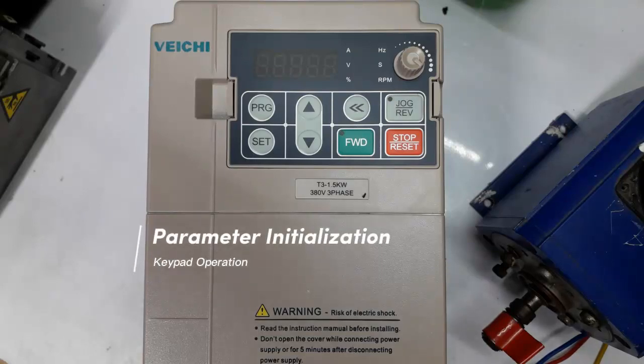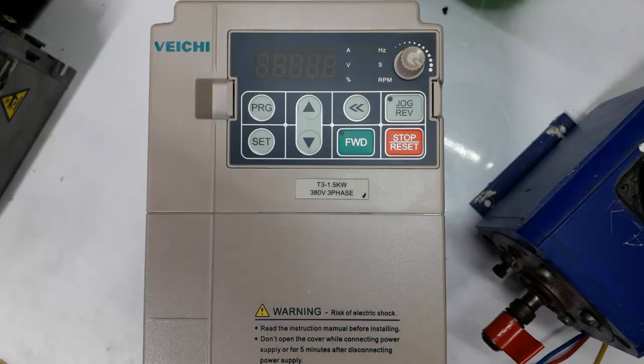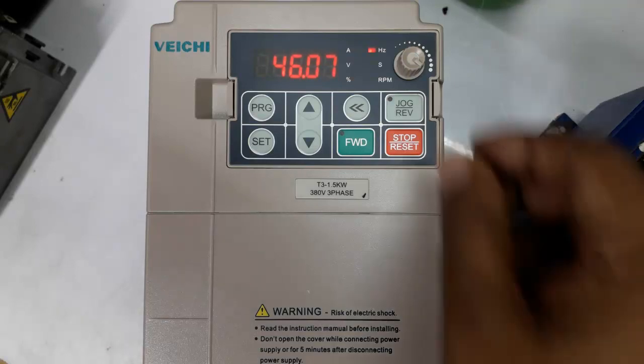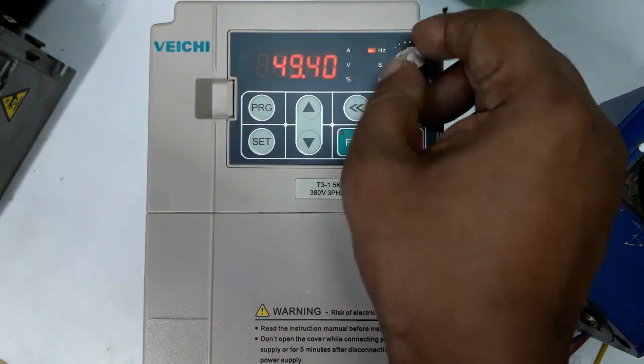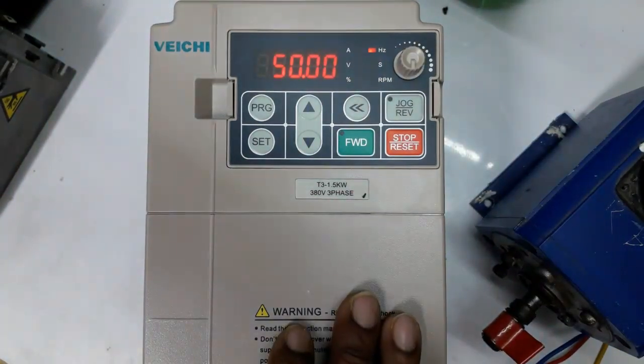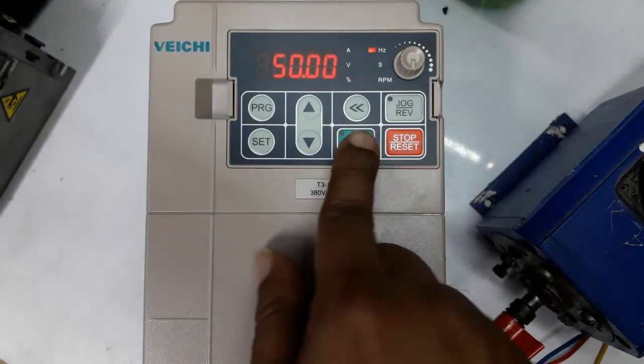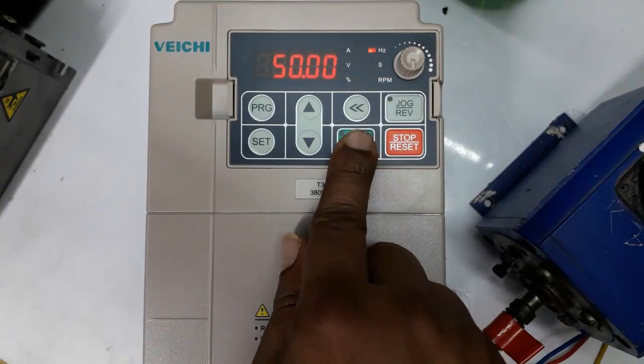VCSC200 drive parameter initialization to activate keypad operation. This drive now has the external run command activated and the keypad potentiometer also activated. So we can run this drive externally. Keypad forward button does not work.